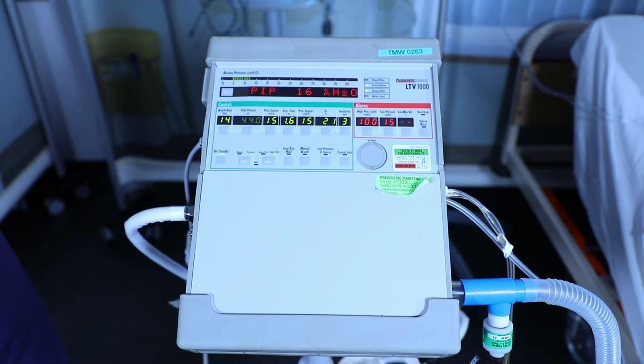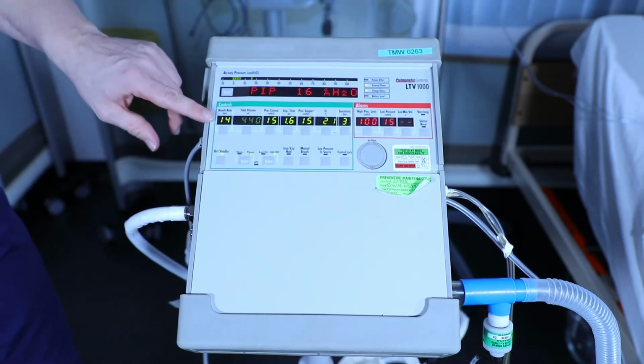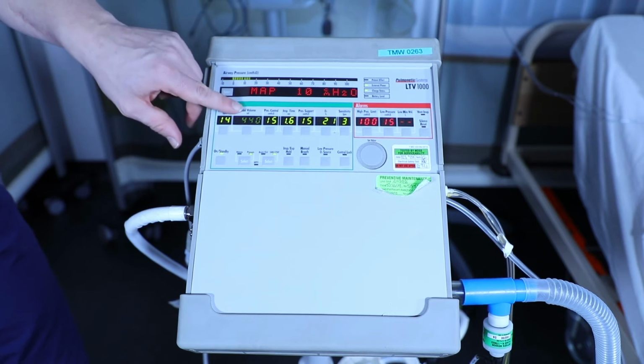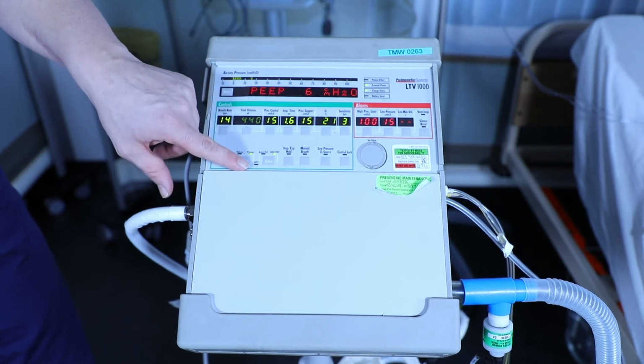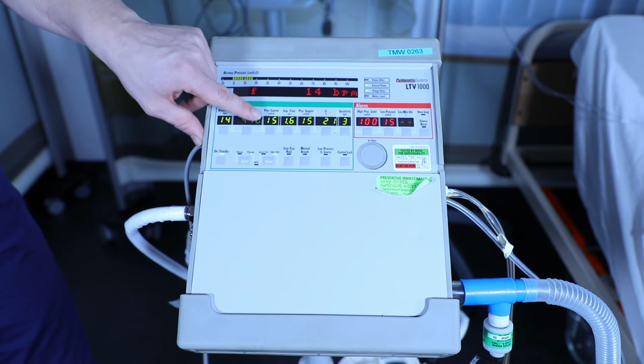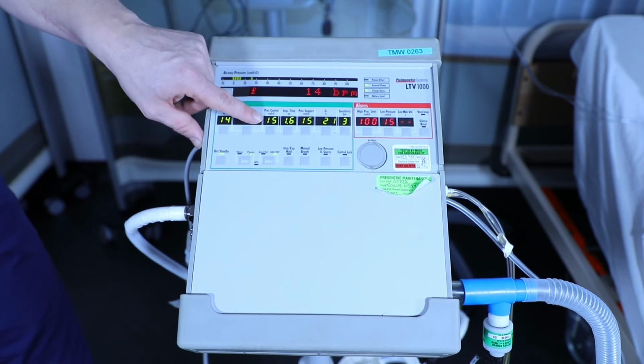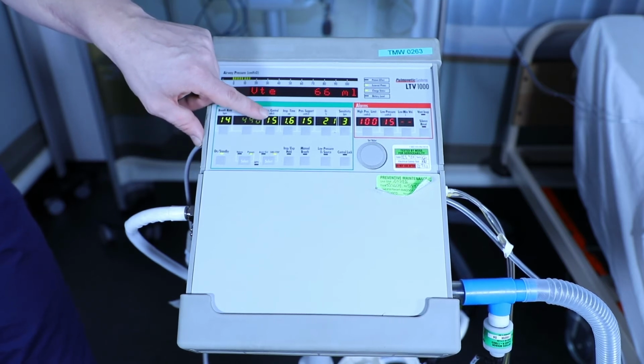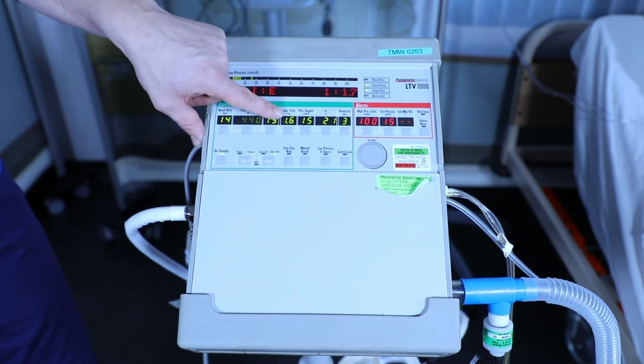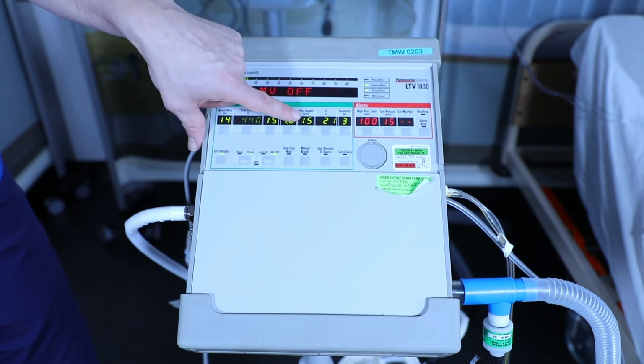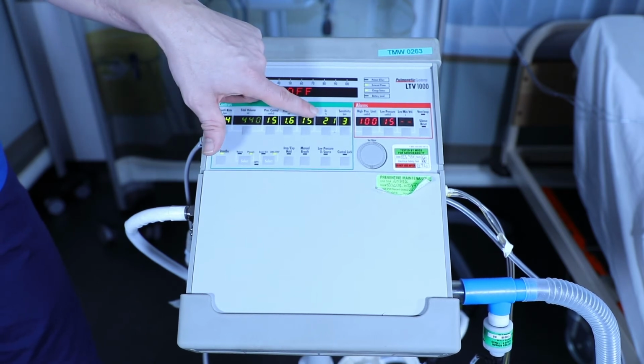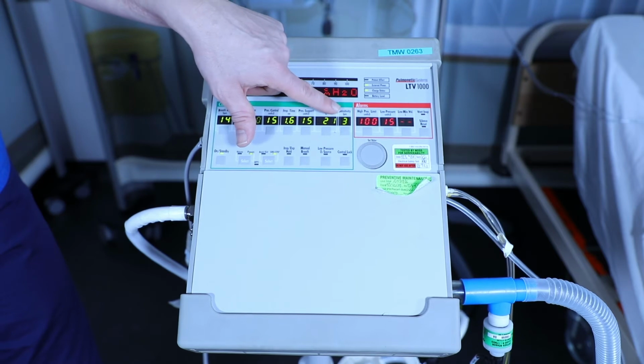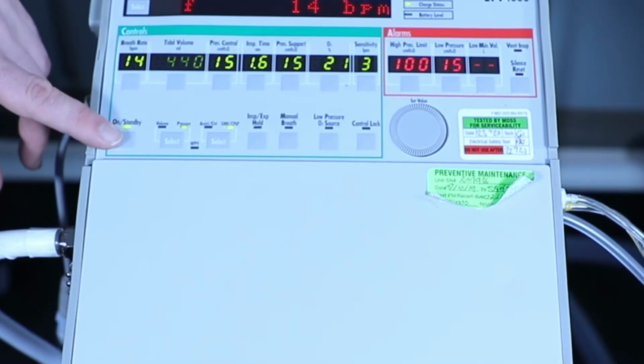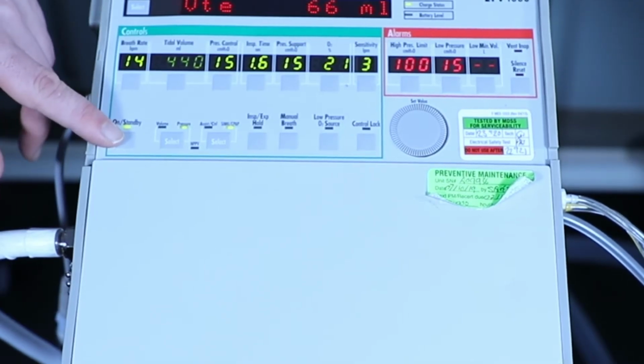So taking a closer look at some of the control options that we have, we've already covered breath rate, tidal volumes, which we could select if we're in a volume mode, which we'll come to in a minute. Pressure control, this is the amount of pressure we are generating to give the patient, so this is controlled rather than what we're given for a support breath. We can change the inspiratory time, pressure support, fraction of oxygen that's been given, and the sensitivity. We've already covered the on-off button.